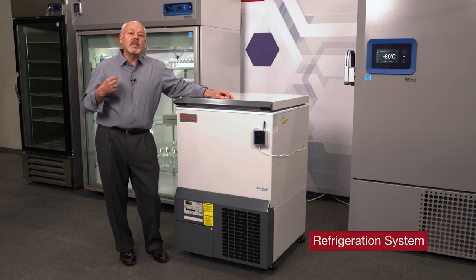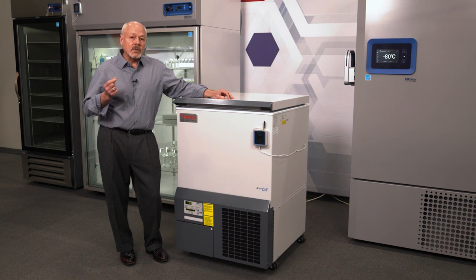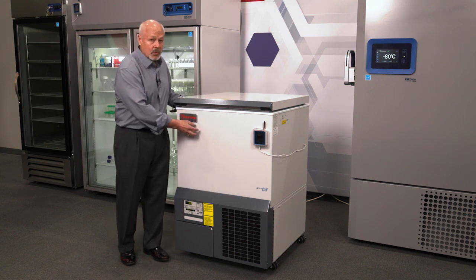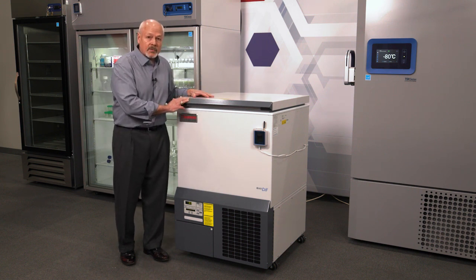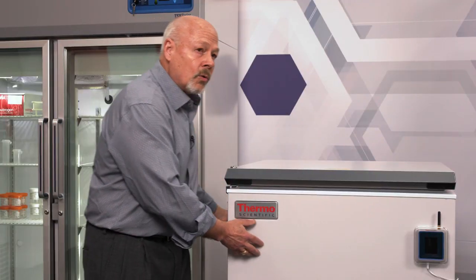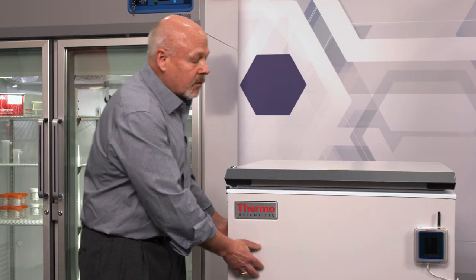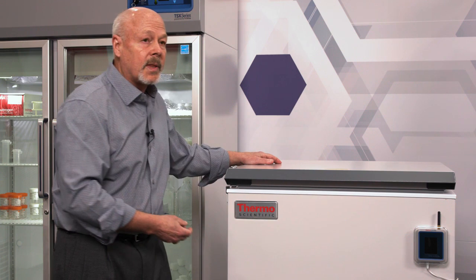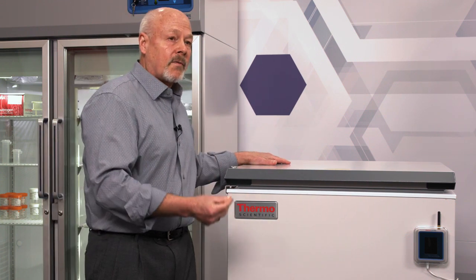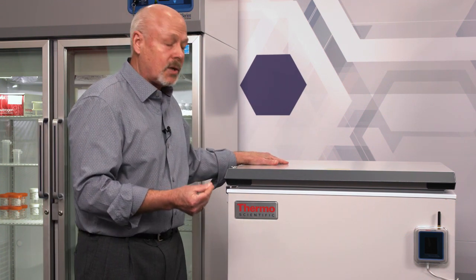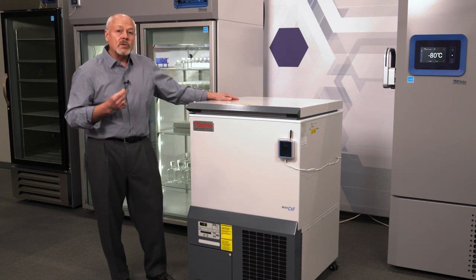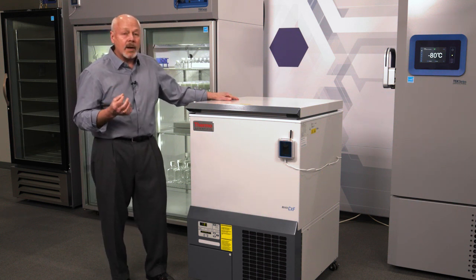This unit utilizes a cascade or 2-compressor refrigeration system. That allows for great power, that allows for uniformity, as well as recovery after door opening. It's called a cold wall system because the refrigerants are flowing between the walls of the system and the base. That also, again, provides very good cooling capacity and uniformity. The insulation used is blown foam, which has great R value.